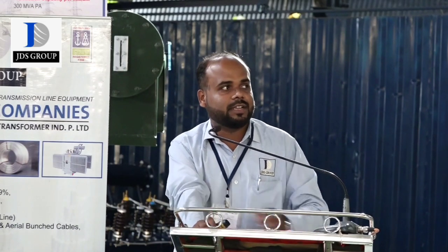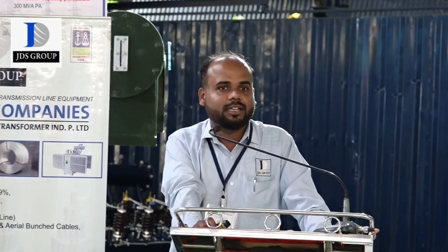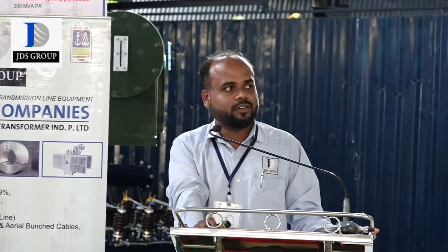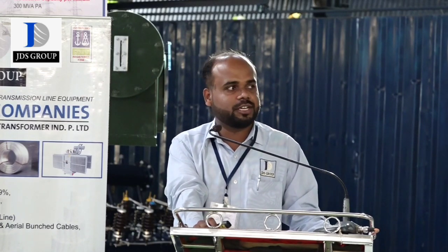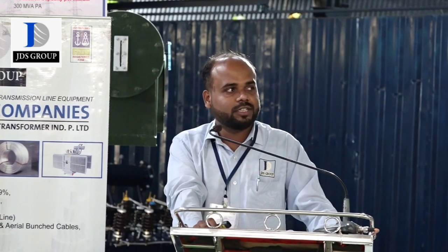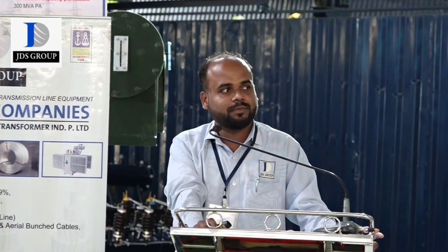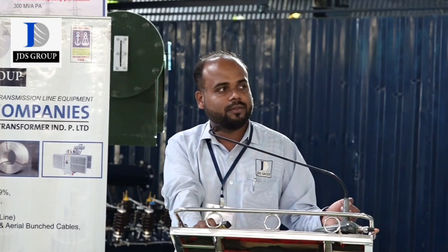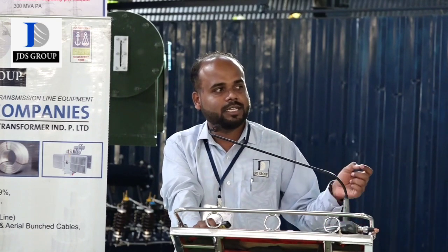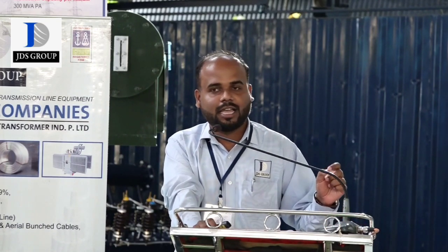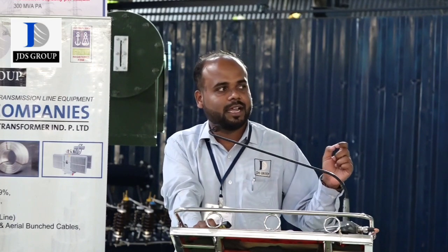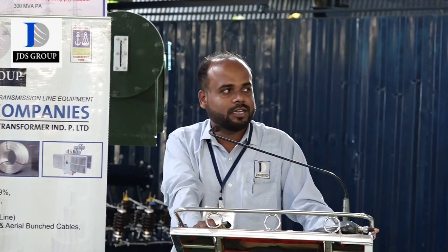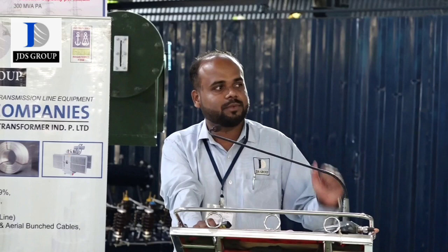Another test is the DVDF test, that is the induced over voltage test. This test is applied on the LV side of the transformer, known as the distribution transformer. Our LV side voltage is 433 volts. In the DVDF case, we provide double voltage, and the double voltage is produced with the help of double frequency. So 866 volts and 100 Hz, as our rated frequency is 50 Hz and rated voltage is 433 volts. So double voltage and double frequency are provided.